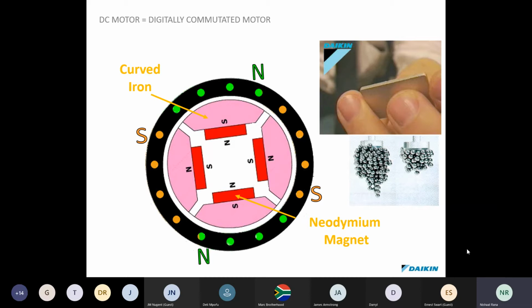And also you've got to think about startup. So what's the worst thing? You've got a power failure, in a large commercial building, and your old non-inverter machines used to take, what, sometimes 15 minutes for a compressor to start up again. So this allows it to start up rapidly again. I might not be 100% confident on the time factor, but I think it's 120 seconds before the machine can start up again.